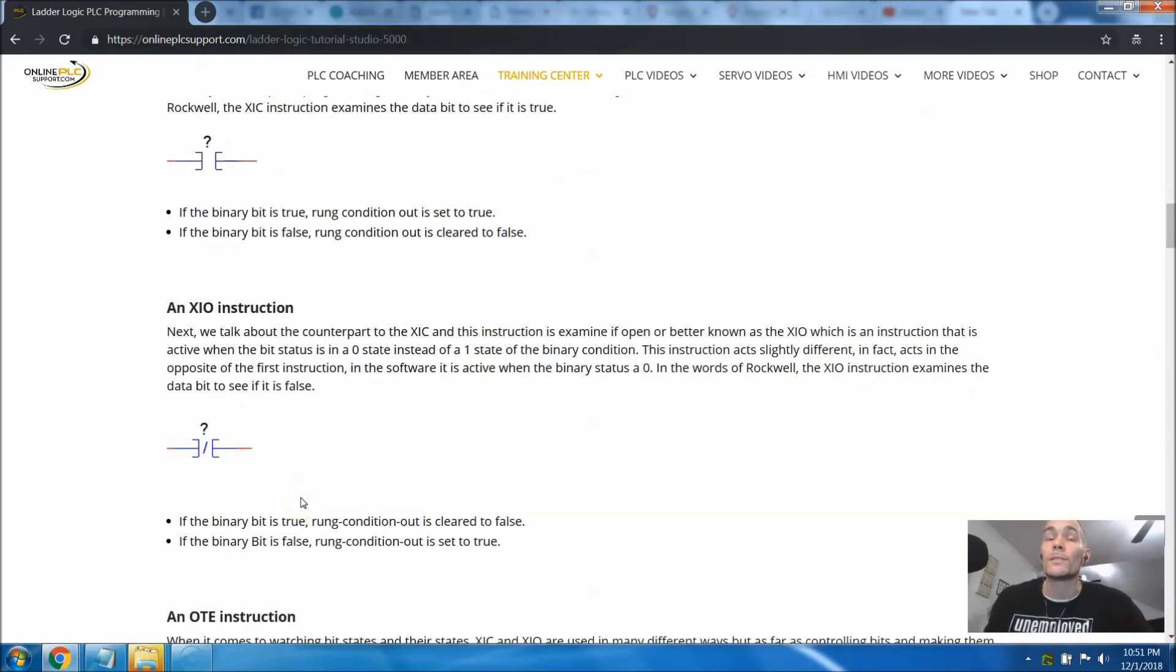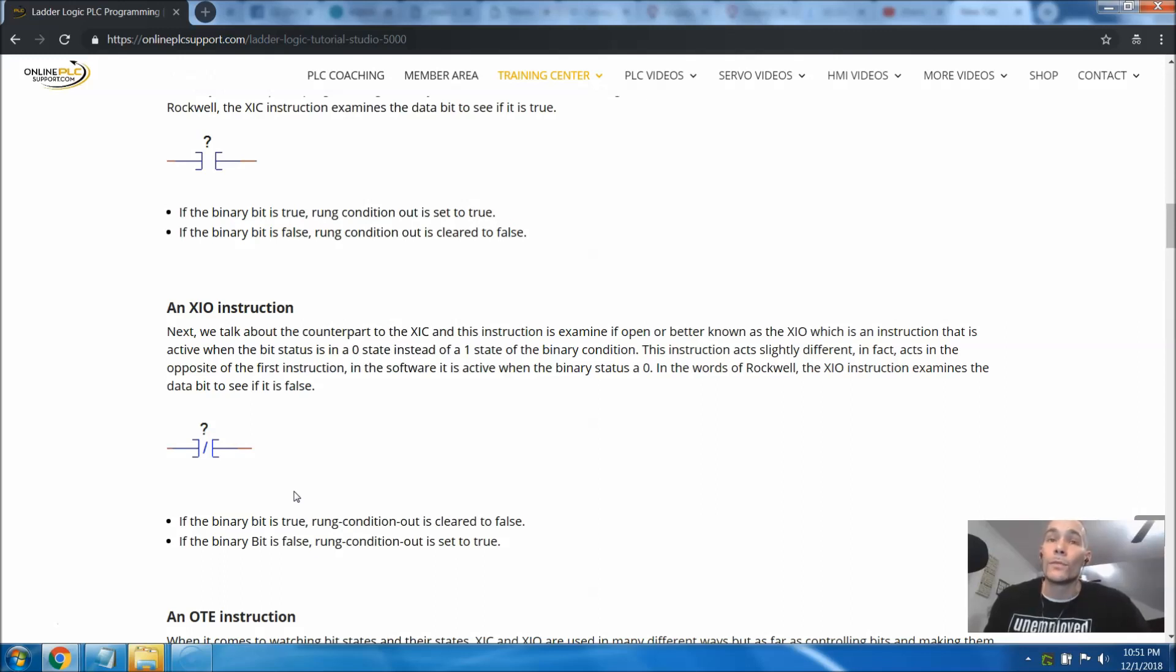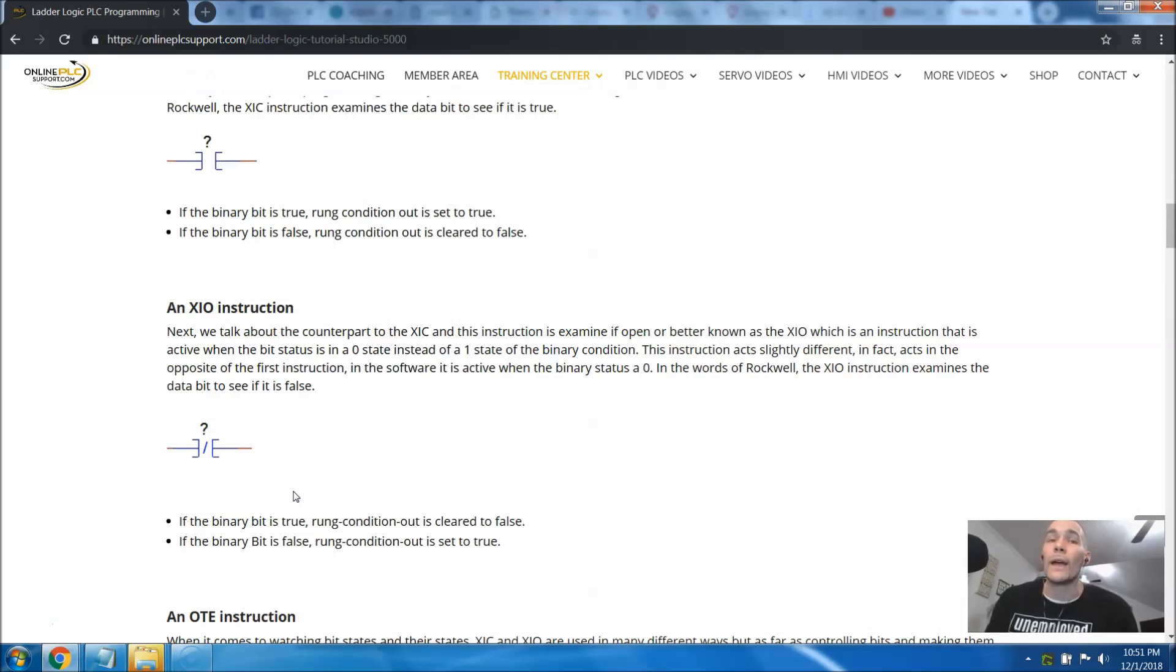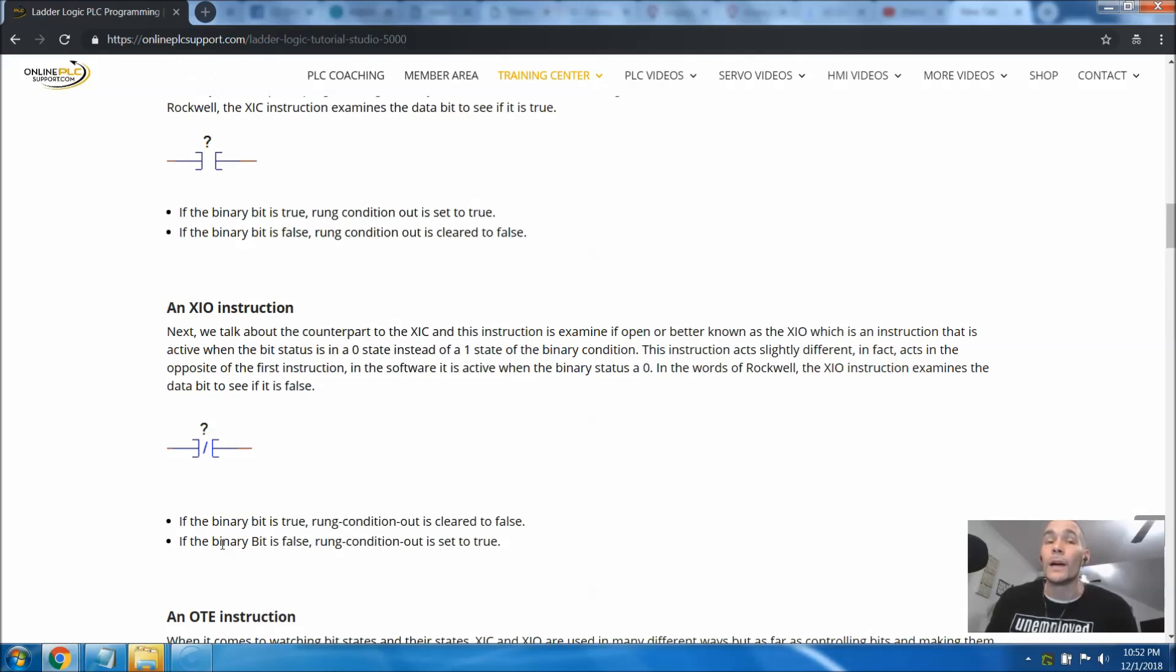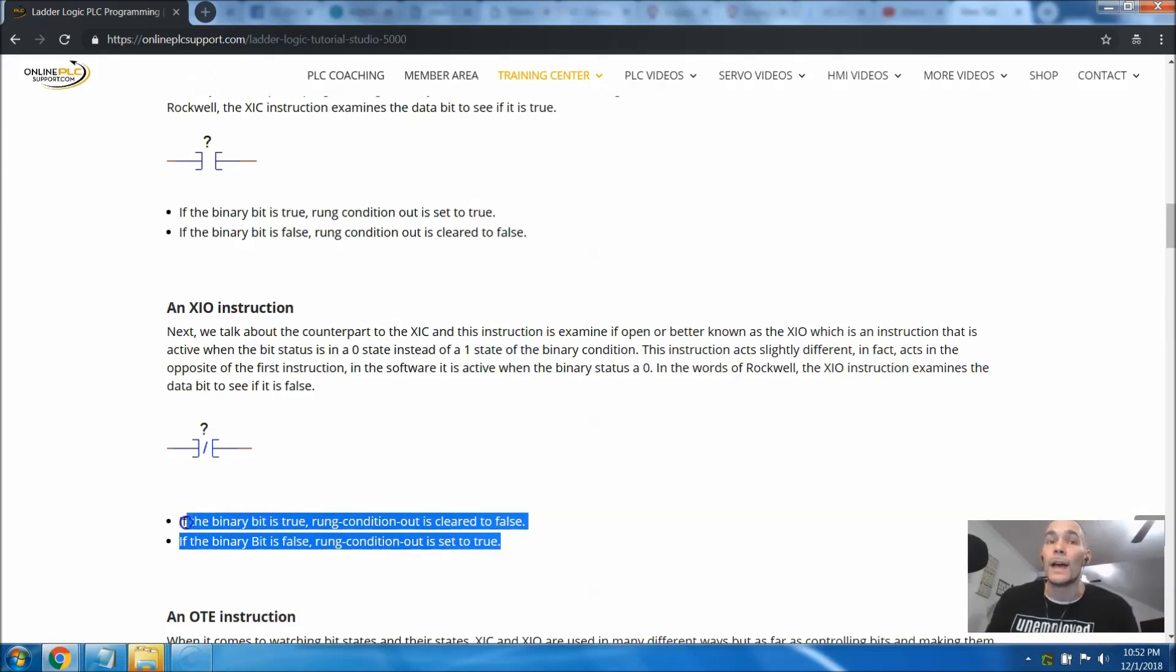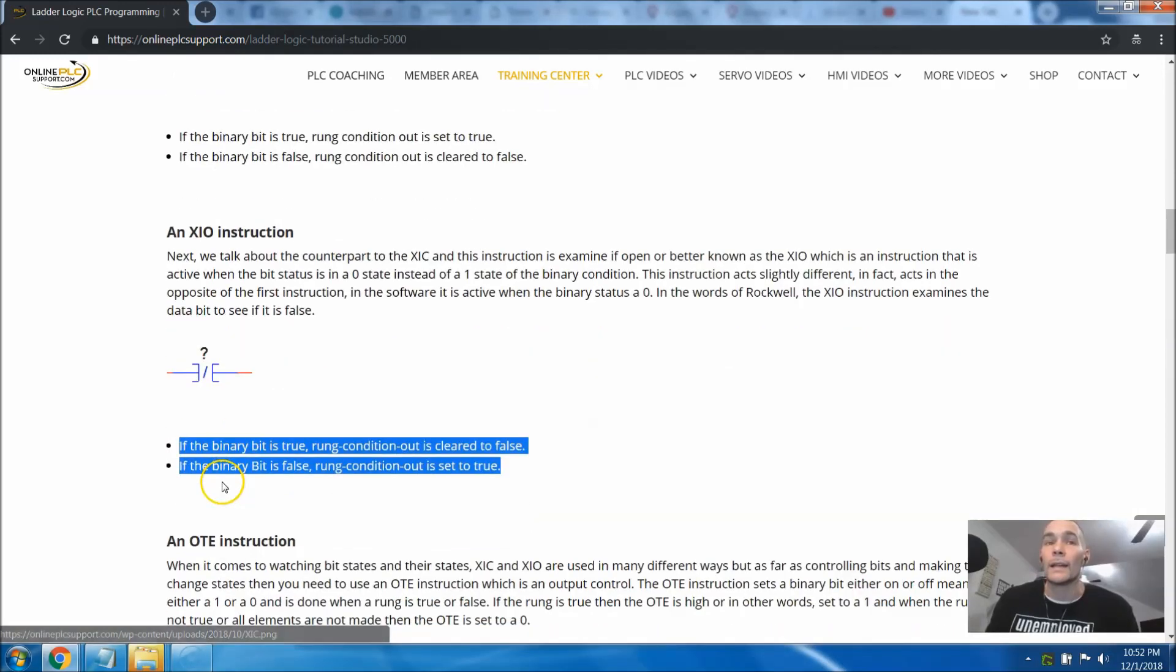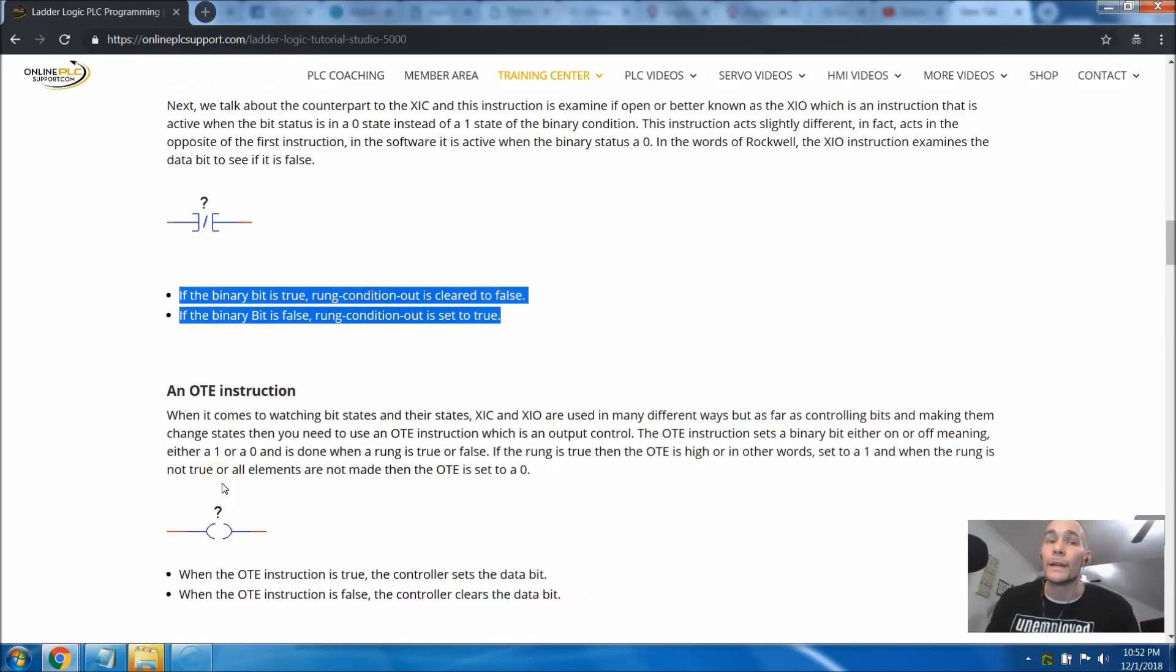If the binary bit is false, the rung condition is obviously cleared to false. The next one, which is the counterpart to that, is the XIO, which is basically an examine if open. So it means you're able to pass power through this rung in the state of zero if the binary bit is at a state of zero instead of a state of one. So therefore, it works counteractive to the first bit that we talked about in the XIC. It's an examine if open, basically. If the binary bit is a zero, then it can transmit power through it.